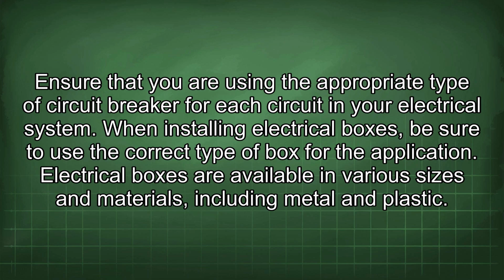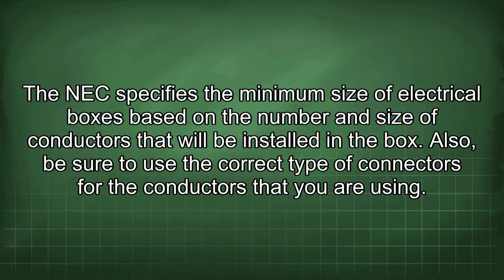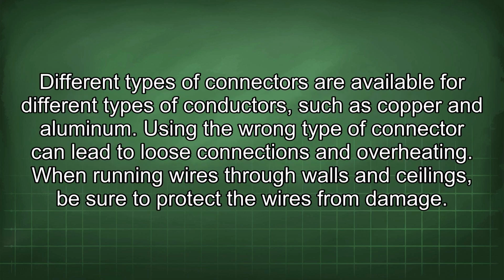When installing electrical boxes, be sure to use the correct type of box for the application. Electrical boxes are available in various sizes and materials, including metal and plastic. The NEC specifies the minimum size of electrical boxes based on the number and size of conductors that will be installed in a box. Also, be sure to use the correct type of connectors for the conductors that you are using. Different types of connectors are available for different types of conductors, such as copper and aluminum. Using the wrong type of connector can lead to loose connections and overheating.